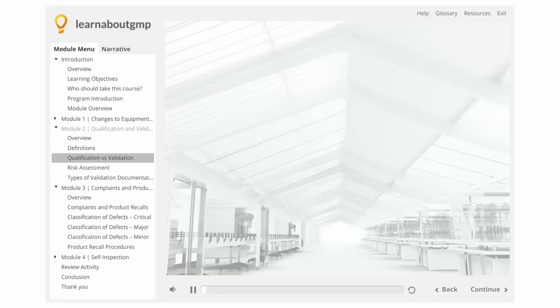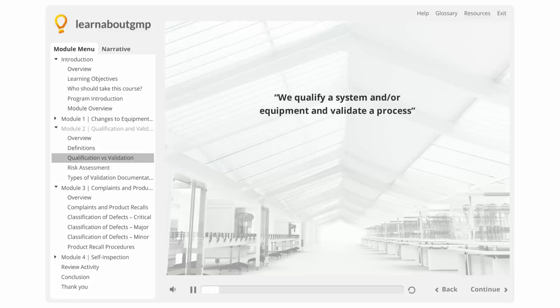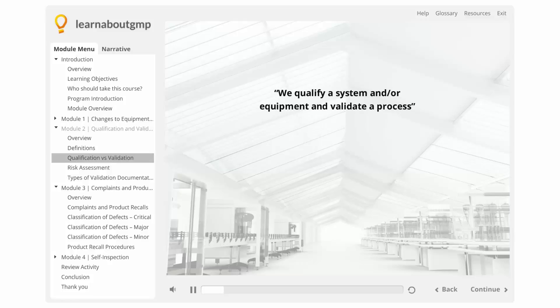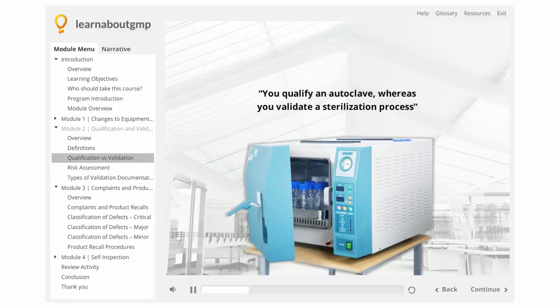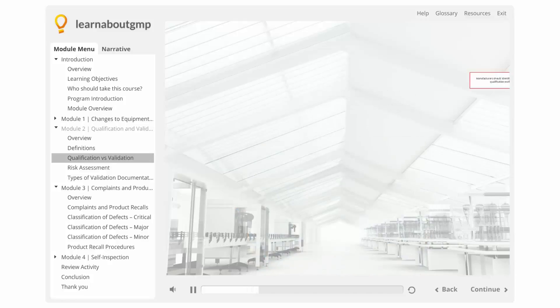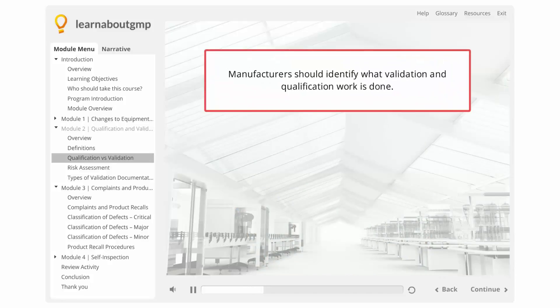There is a general saying within the life sciences: we qualify a system and/or equipment, and validate a process. A system and/or equipment must be qualified to operate in a validated process. For example, you qualify an autoclave, whereas you validate a sterilization process.